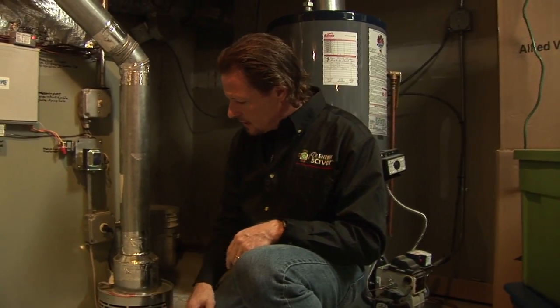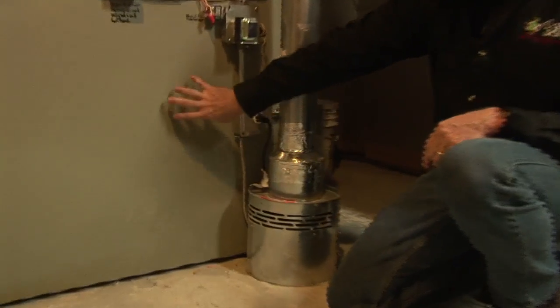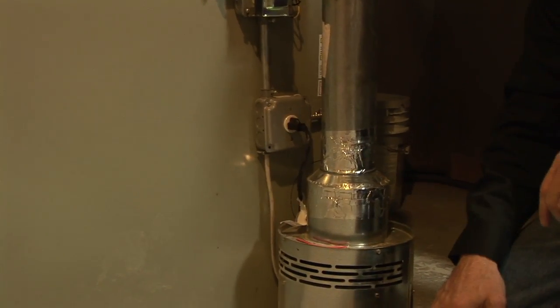So this is a good thing for an atmospherically vented oil appliance, but not nearly as good as high efficiency equipment that has sealed combustion and direct vent from the outside to the appliance and from the appliance back to the outside with no effect on the interior air at all.